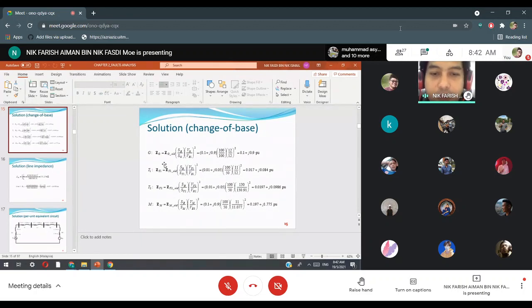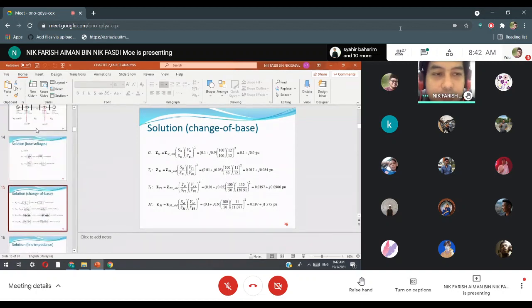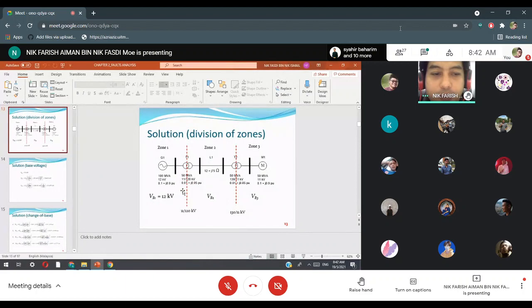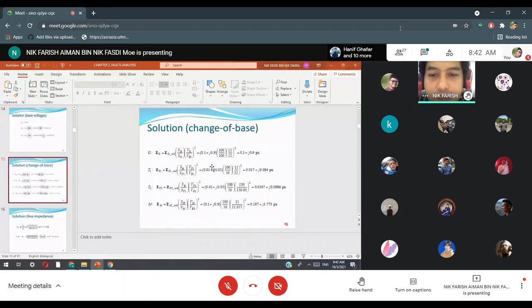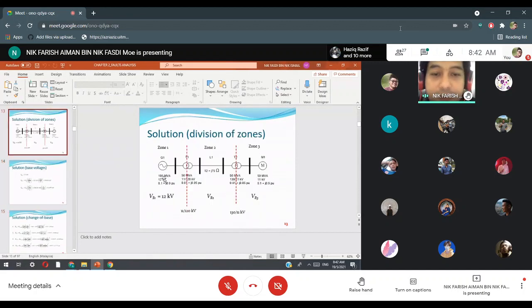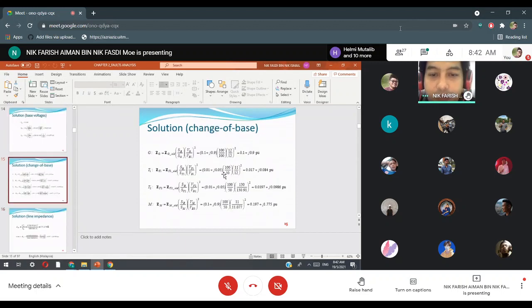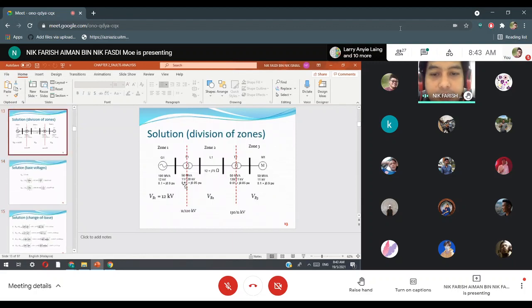Okay, for T1 it's the same, but now we substitute this formula for Z_T1. Same thing - Z_T1 refers to the question here: transformer 1 is 0.01 plus j0.05. S_base is 100 MVA - where does this come from? Because we refer to G1, so 100 MVA divided by the transformer 1 rating, which is 50 MVA.